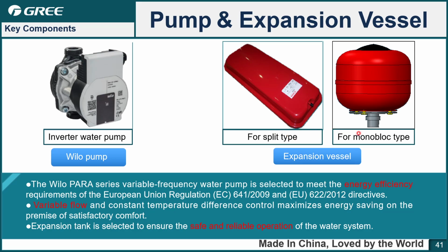For the expansion vessel, there are two types. For the split type and all-in-one type, it's the flat expansion vessel. However, for the monoblock type, it looks like a cylinder. Yeah, these are the two expansion vessels for split and monoblock. The expansion vessel is used for water storage to keep the water pressure in the system stable, and also for water expansion. If the temperature increases, some water may expand. We need a water tank to store the additional water.